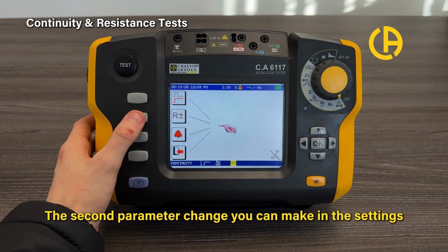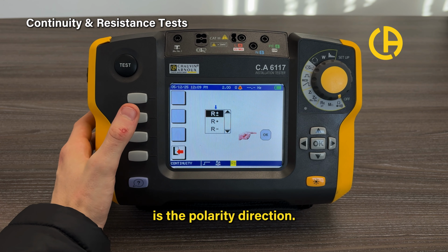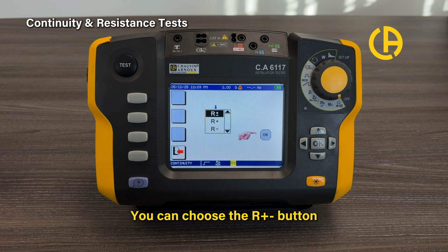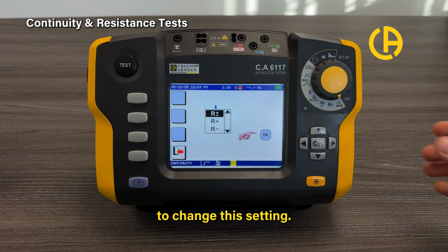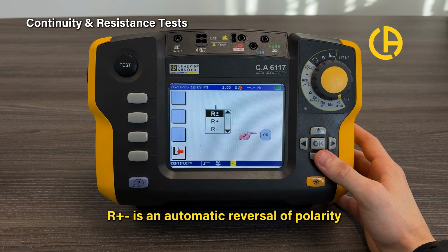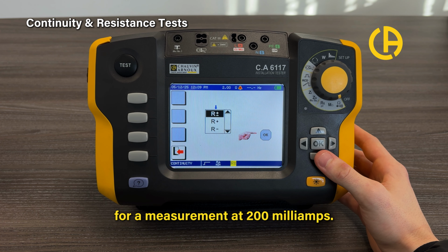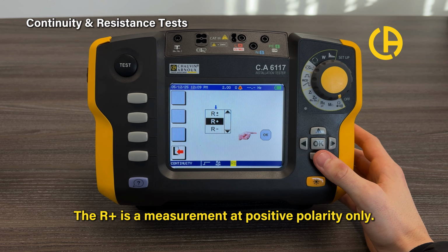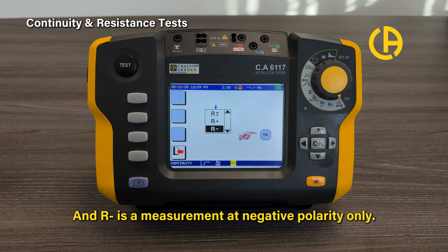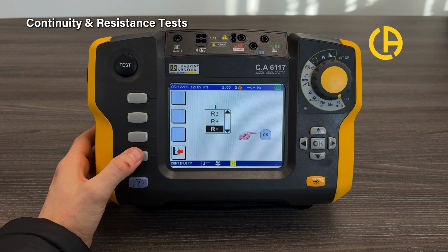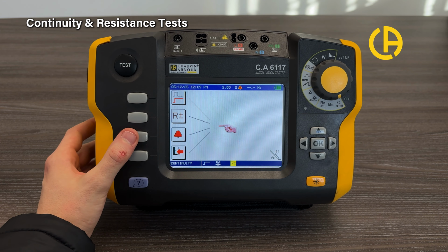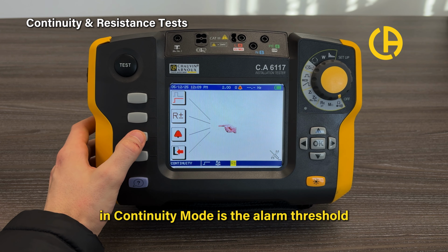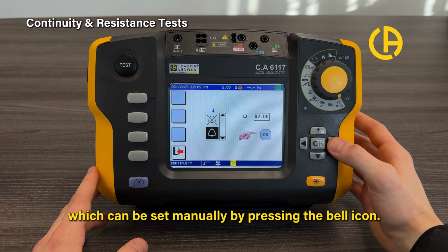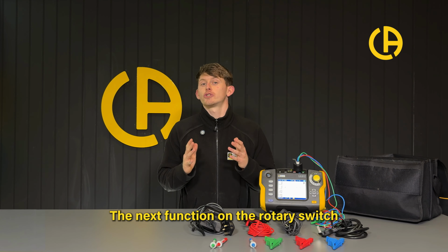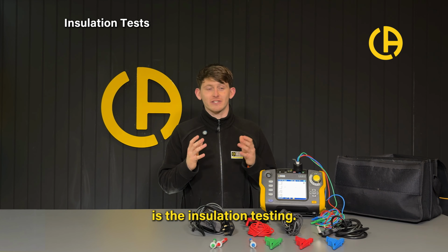The second parameter change you can make in the settings is the polarity direction. You can choose the R plus minus button to change this setting. R plus minus is an automatic reversal of polarity for a measurement at 200 milliamps. The R plus is a measurement at positive polarity only, and R minus is a measurement at negative polarity only. The last parameter change in settings in continuity mode is the alarm threshold, which can be set manually by pressing the bell icon. The next function on the rotary switch is the insulation testing.